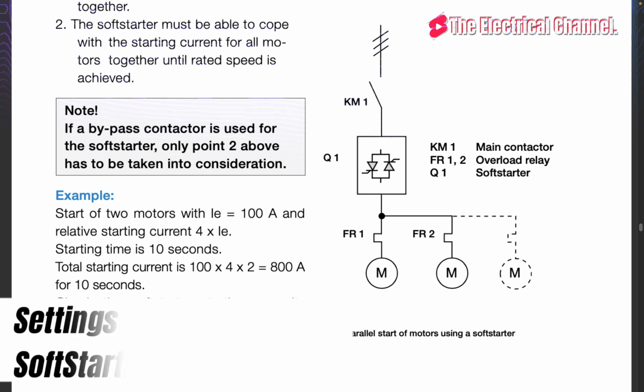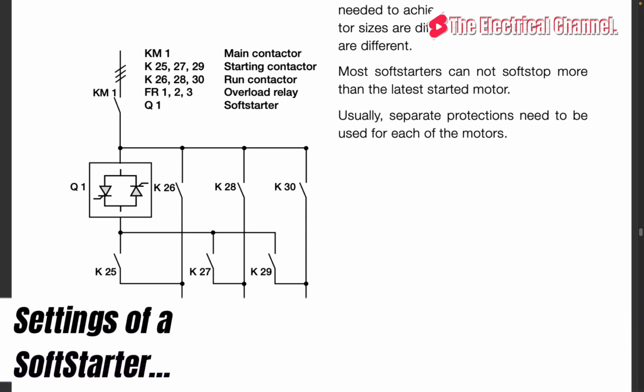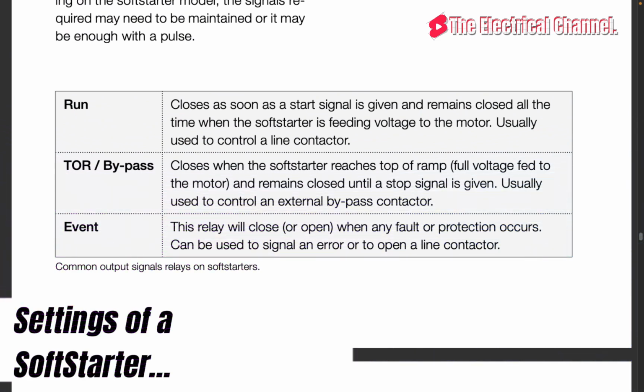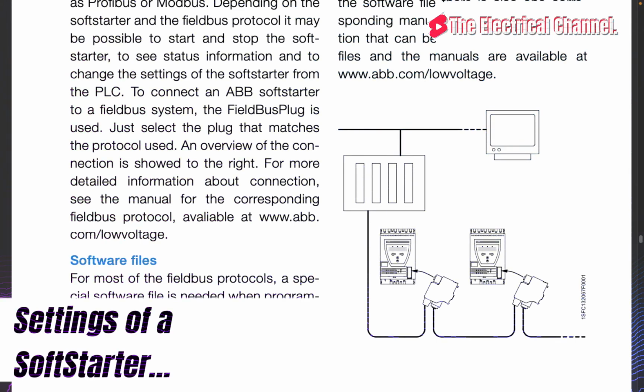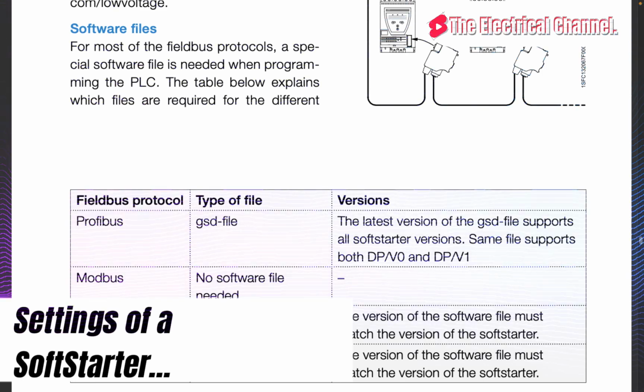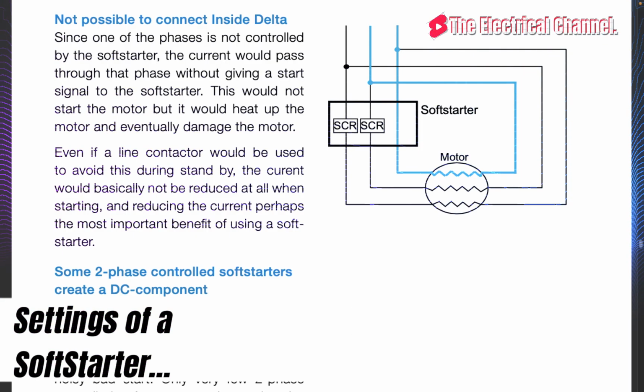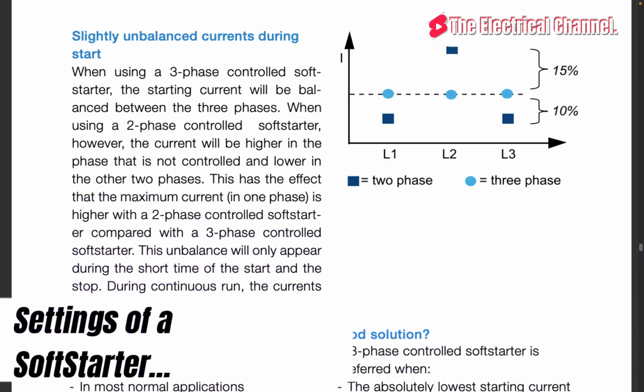The settings can be done either by adjusting potentiometers, changing dip switches, using a keypad, or a computer. Start ramp is the time from where the softstarter starts its ramp, or initial voltage, until full voltage is reached. The ramp time should not be too long, as this will only result in unnecessary heating for the motor and a risk of the overload relay tripping.